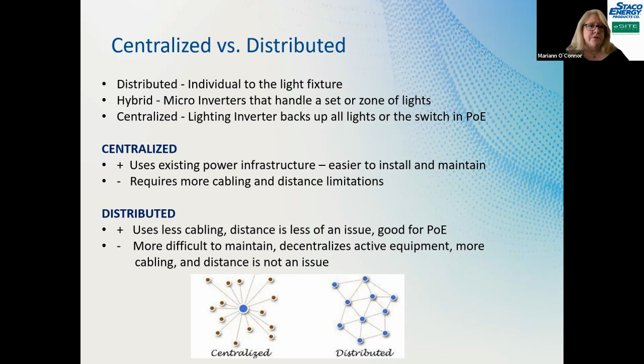And on centralized installs, you're using existing power infrastructure. They're pretty easy to install. They're easy to maintain. You do have a little bit more cabling. There are some distance limitations. On the distributed, you definitely use less cabling. Distance is not really an issue, but at the same point in time, it's a lot more to maintain. So you kind of have to look at the pluses and minuses, but we certainly see where the centralized inverter definitely handles the ease of maintenance for the emergency lights. Okay, so next slide.